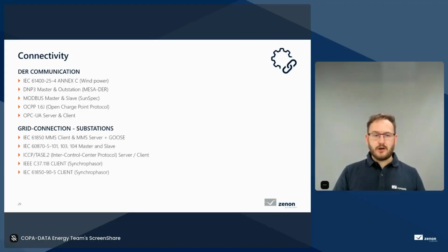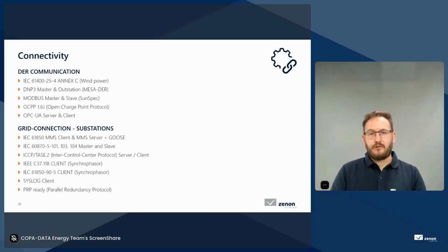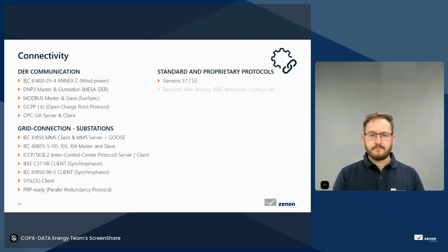When it comes to the grid connection, then here we have our IEC 61850 MMS client, but also an MMS server, also supporting GOOSE. So it's a webinar about DERs, but extremely beneficial to have a GOOSE publisher subscriber for various use cases within the substation HMI as well. And various other protocols which are typically found in the substation automation sector.